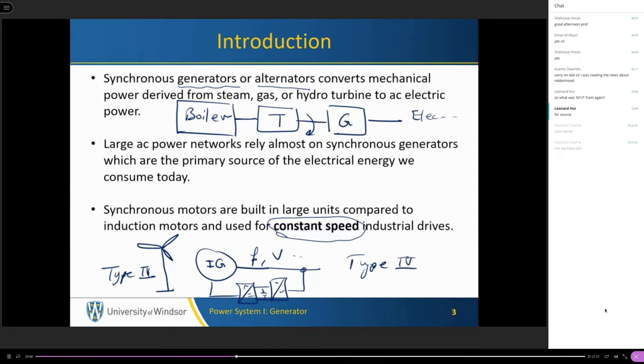Type four uses a synchronous generator, but variable speed. The power electronic converters will be installed on the stator, not just the rotor. Here we have the rotor, and here we have the stator of the machine. So we need a power electronic converter at high capacity that actually handles the full rating of the machine. There are other types of wind turbines, like type 1 and 2. Those types are fixed speed or have limited control over the speed of the machine.